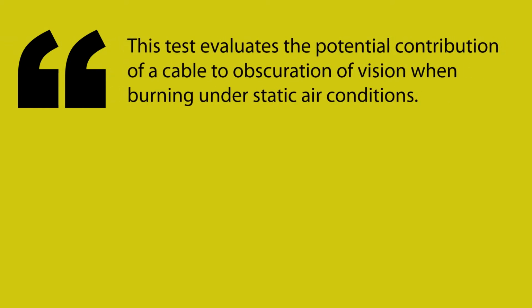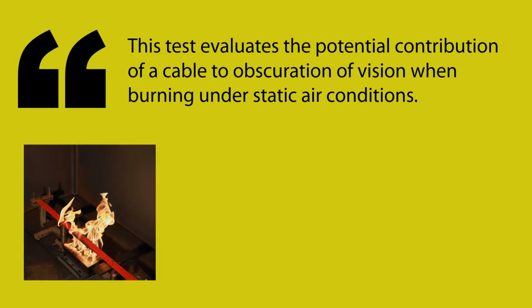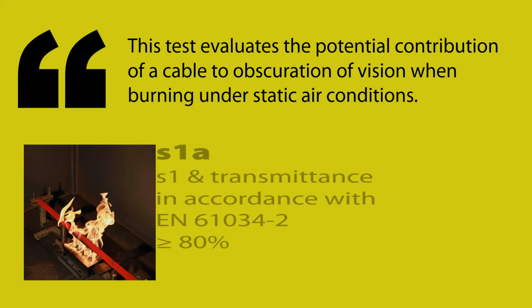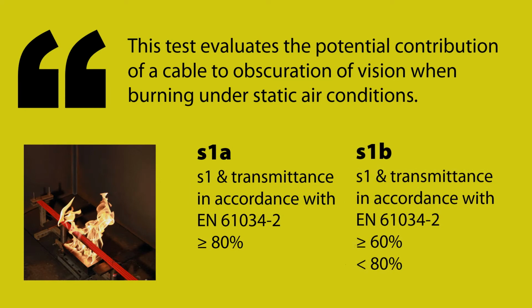Now to clear up any confusion. If you pass S1, you can then opt to add an additional test to establish what is termed transmittance. This test is not new to us, and we've been using it for a number of years to qualify an LS0H cable, and it is related to smoke opacity or density. Effectively, it is the amount of light that can be measured through the smoke produced.